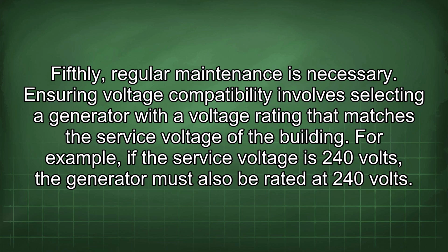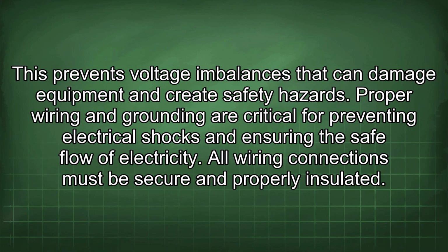Ensuring voltage compatibility involves selecting a generator with a voltage rating that matches the service voltage of the building. For example, if the service voltage is 240 volts, the generator must also be rated at 240 volts. This prevents voltage imbalances that can damage equipment and create safety hazards.